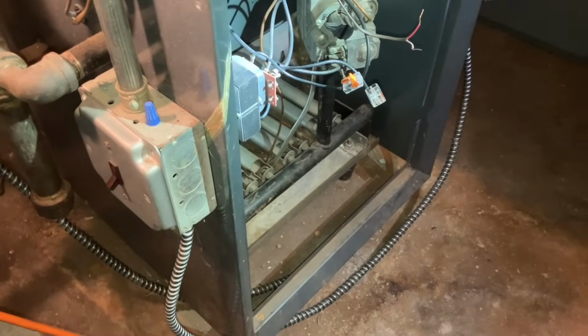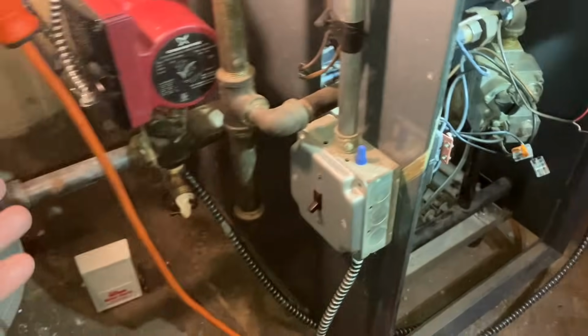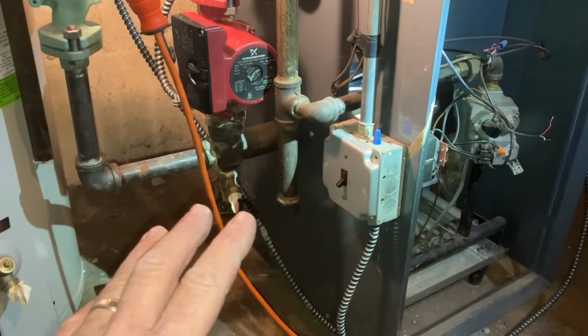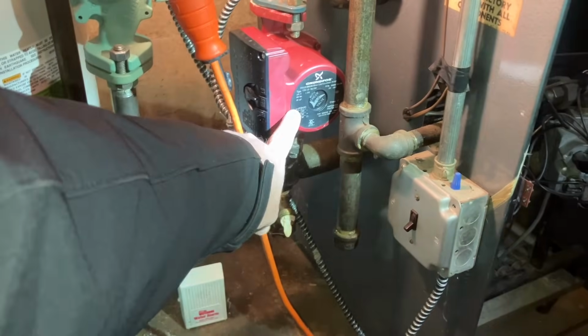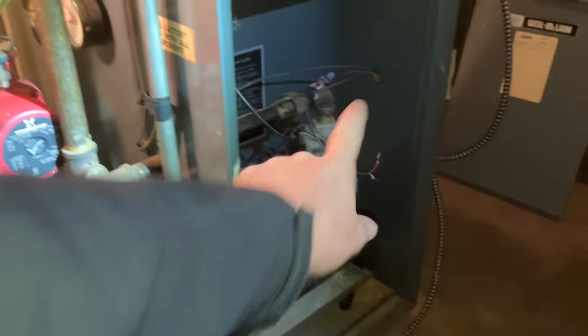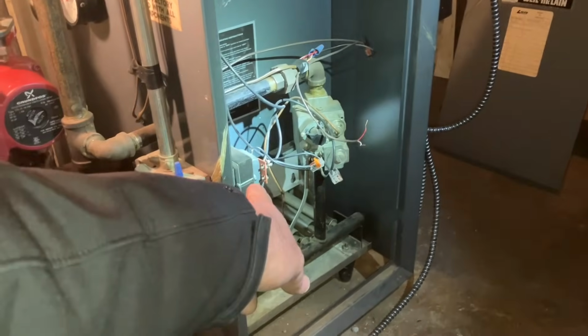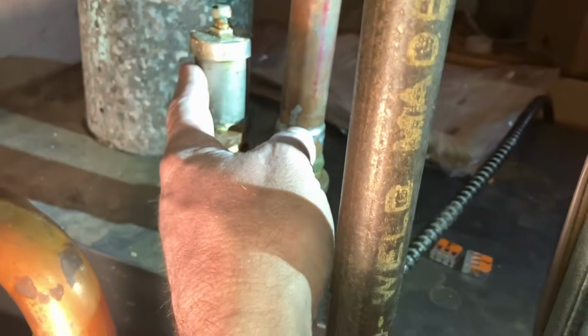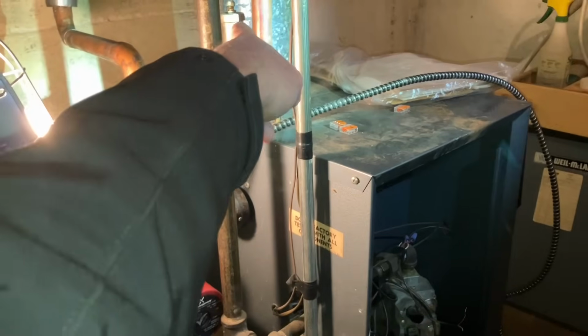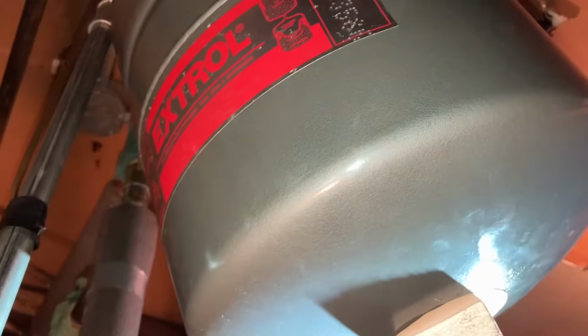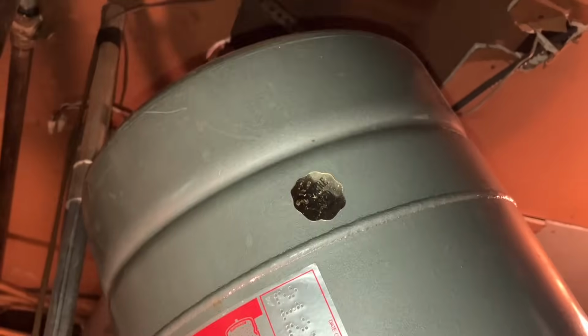it'll run forever. You'll replace components, and the only thing that it looks like has been replaced from the original install is probably this circulator. Yeah, that's not the original circulator. Right. That gas valve looks original. Yeah. That fan center relay looks original. This is probably not original. Probably not. I don't remember that. It's from 1980, so I don't think that looks original. But this expansion tank, I'm willing to say the expansion tank is original too. I'm almost certain of that. Right? Yeah. There's actually a serial number on there.